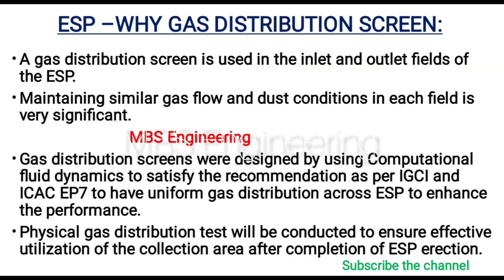Now we understand why a gas distribution screen is required in the electrostatic precipitator. Point 1: A gas distribution screen is used in the inlet and outlet fields of the ESP. Point 2: Maintaining similar gas flow and dust conditions in each field is very significant. Point 3: Gas distribution screens were designed using computational fluid dynamics to satisfy the recommendation as per IGCI and ICAC EP7 to have uniform gas distribution across the ESP to enhance performance.